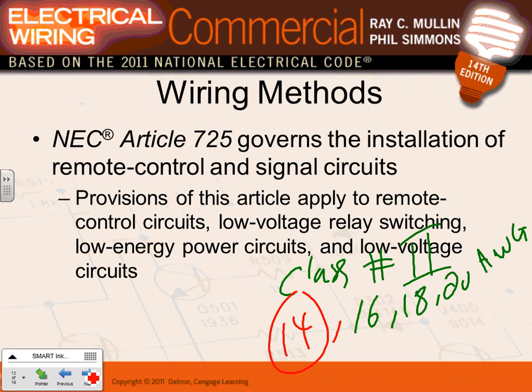Okay, so the conductors that we use, guys, are 16, 18, and 20. Article 725 takes care of you. The only thing I want to say about Article 725 is that it tells you very simple things. Could you please separate these wires from the power and lighting and equipment? That's it. And if you're putting them in a ceiling like this, a plenum ceiling, could you please make them plenum-rated cables, meaning if there's a fire, they don't contribute to the spread of fire or to the smoke?